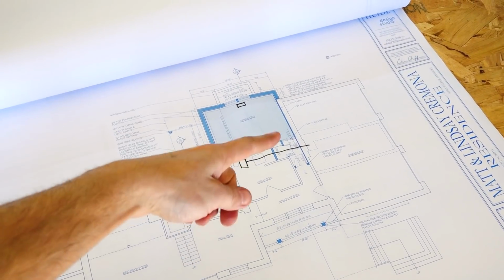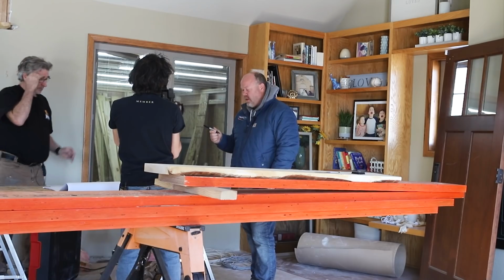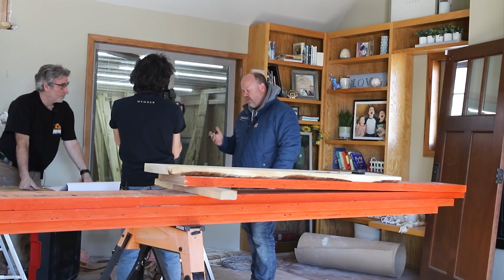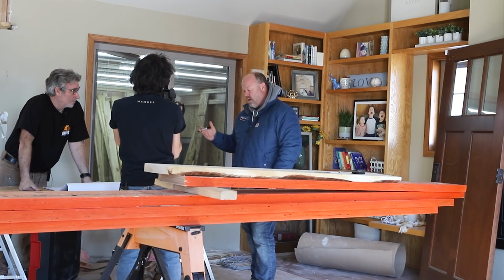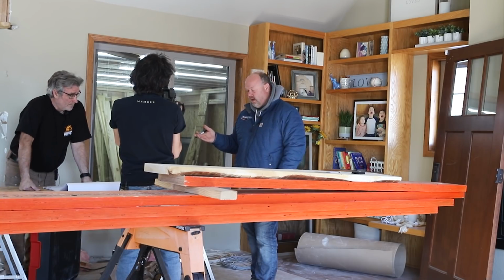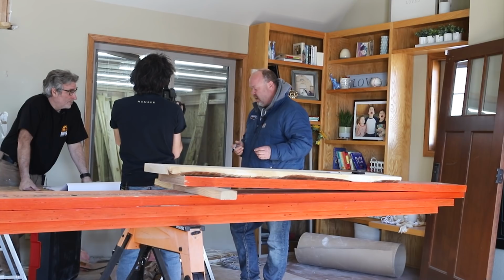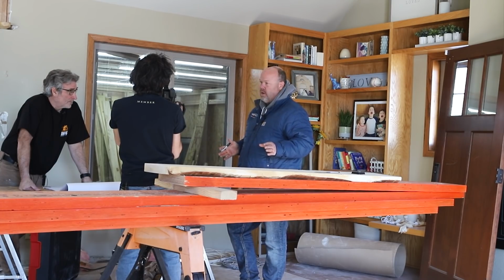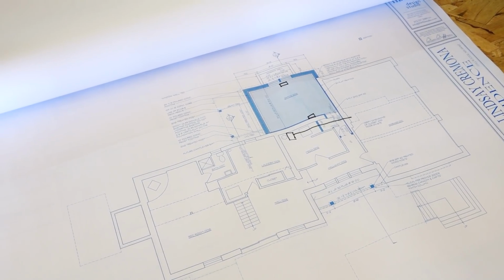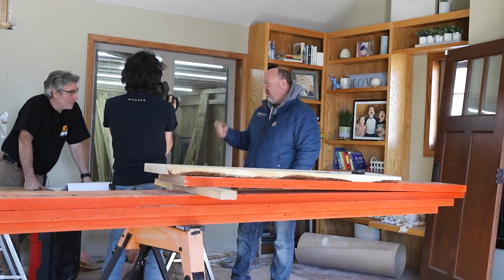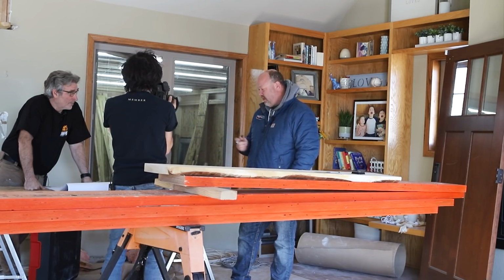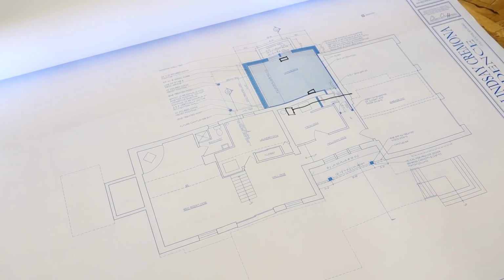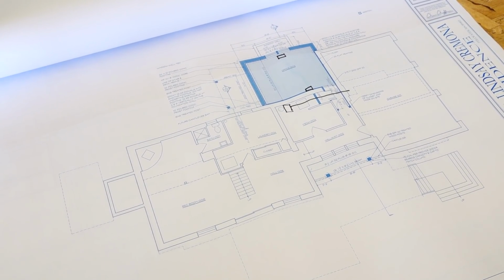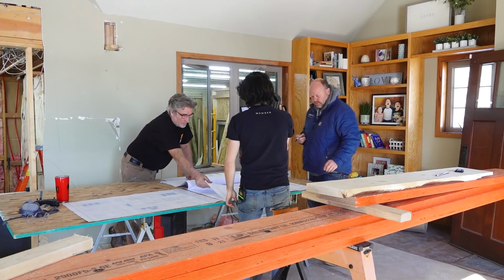Yeah. Just recirculating. You know, we size basically for about 1,200 feet per minute in the main trunk line, and we try to be between 600 and 900 feet per minute on the branch runs. And if we vary on that, if we're lacking, we're not going to get a full throw out of that register, and that's going to create comfort issues. In the dead of summer, you might need it, but with the insulated foundation, which is unbelievable, and the return, it's going to maintain a very, very comfortable temperature in there.